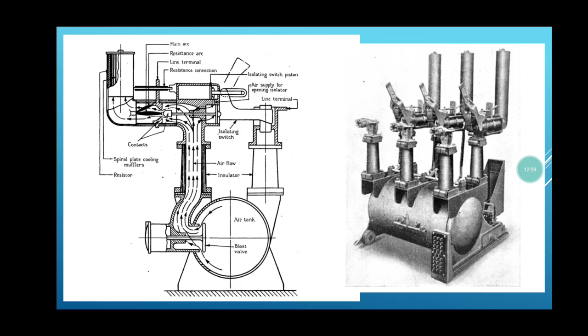Types of air blast circuit breakers. There are mainly three types of air blast circuit breakers: axial blast type, cross blast type, radial blast type. In axial blast type, the air blast is directed along the arc path. In cross blast type, the air blast is directed at right angles to the arc path. In radial blast type, the air blast is directed radially.